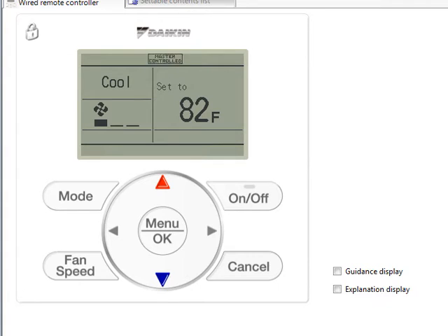What is seen now is a Daikin VRV wall controller, remote controller. You'll notice that in the top center of the display there is an icon flashing that says master controlled. This is the natural state of all fan coils of a freshly commissioned Daikin VRV system.